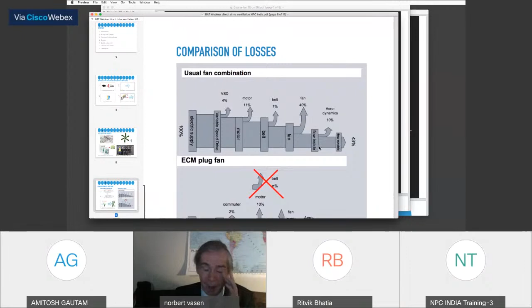With an electronically commutated motor and plug fan, you have 100% electricity but fewer losses, because every component is designed in a monoblock for each other. You don't have a belt. So at the end you have 57% as an example in the airflow. That's a third more compared with the 43% of the old system.